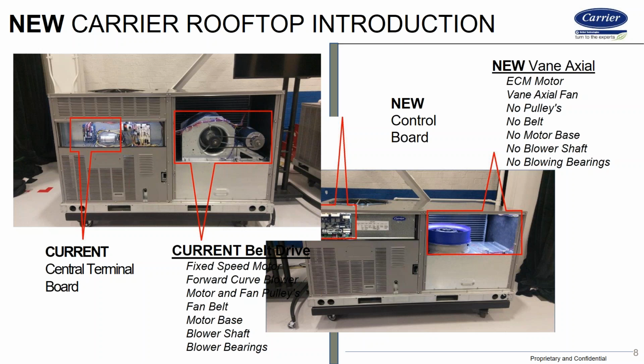All right. Any other questions? We do have a question from Antonio. How would you adjust this motor with a zoning system? Well, you would have to set it like any zoning system. When you set up a unit, you have to set it at full CFM. So you'd have to drive all your zone boxes or dampers wide open and set up the static there.